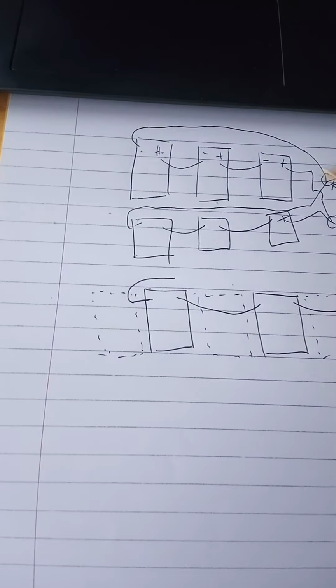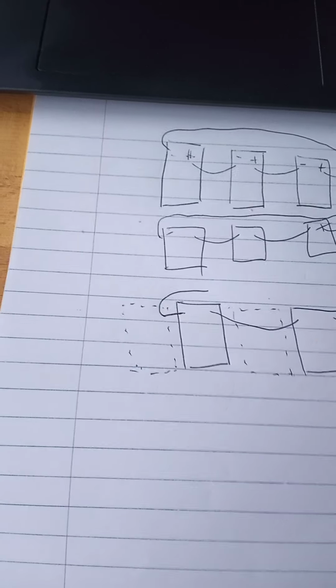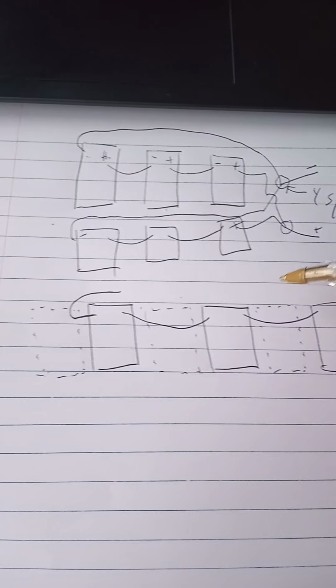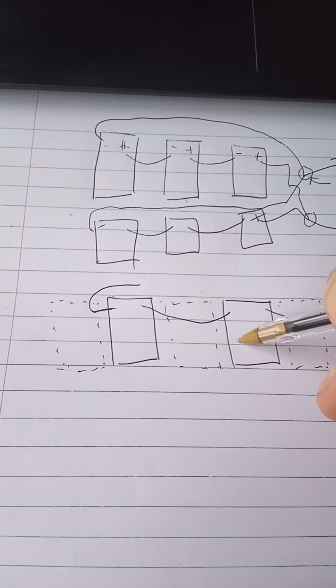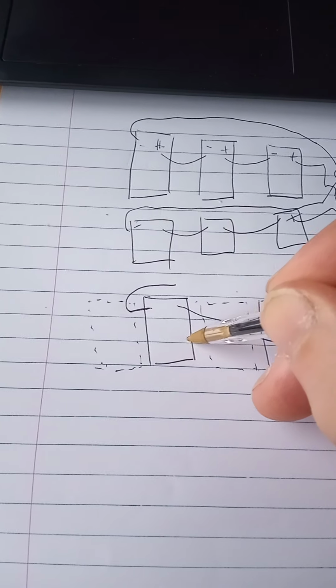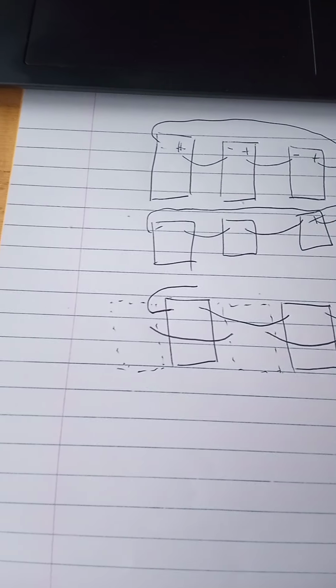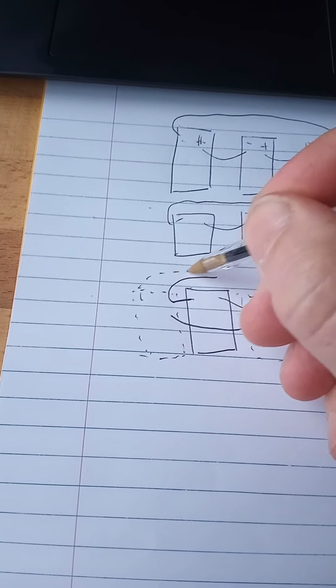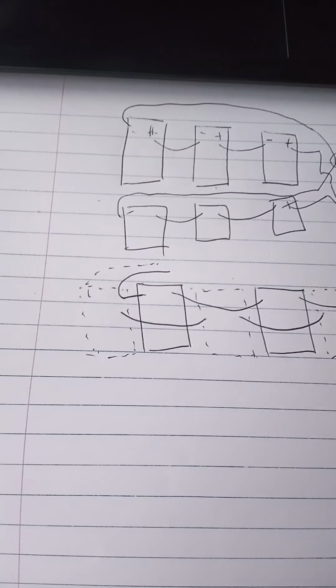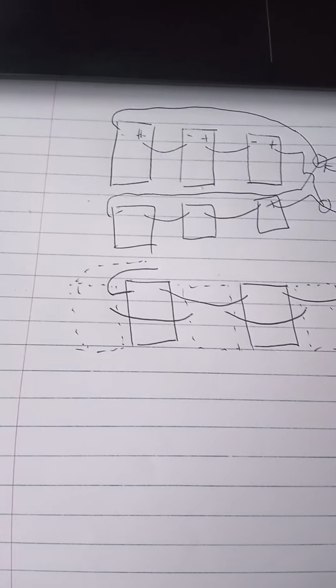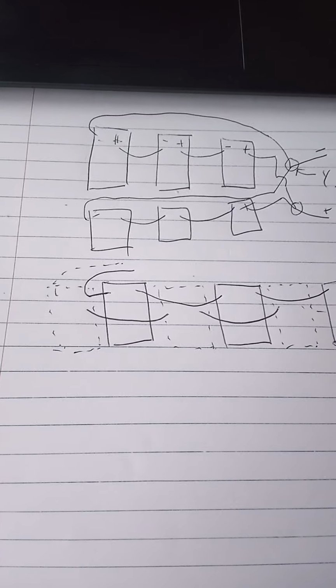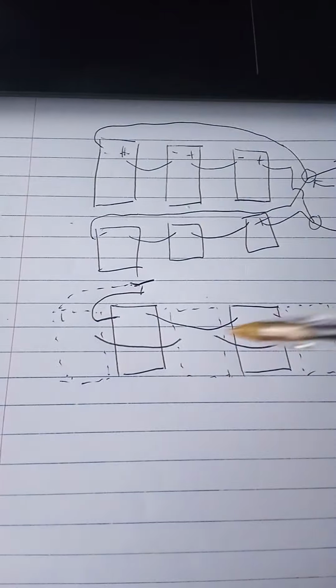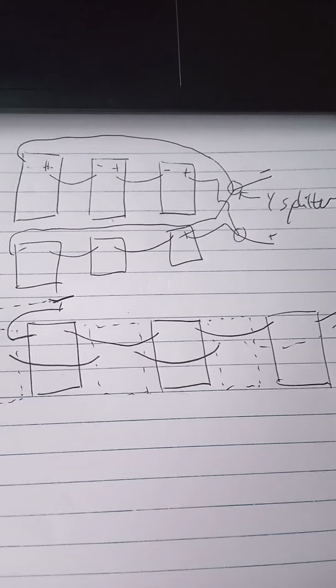So this was going off here. So now I'm going to go, okay, here's my 3 additional panels. I'm going to go from one to the next, to the next. Now I've got my negative here and my positive here. And the Y splitter, the paralleling point for the two systems, is then within reach of both panels at either end without using additional cable. So that's a little trick for you.